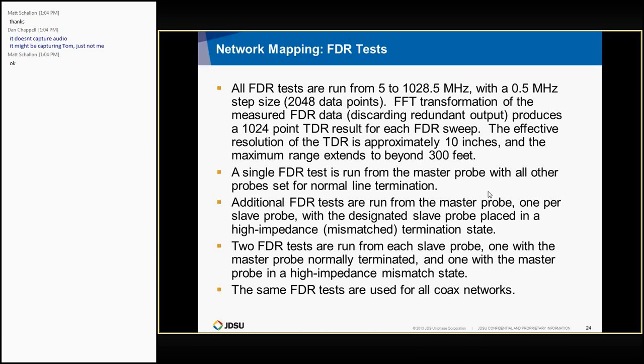Then we run the single sweep from the master with all of the probes in normal termination. Then you run another FDR test from the master for each slave, with that slave placed in a high impedance mismatch state. Then two tests are run for each slave probe, one with the master probe normally terminated and one with the master probe in a high impedance mismatch state. And the same FDR tests are used for all applications, the DSAM, Smartid, they all work the same in that way.